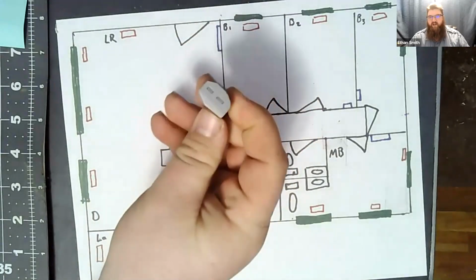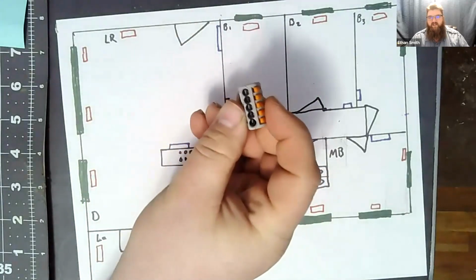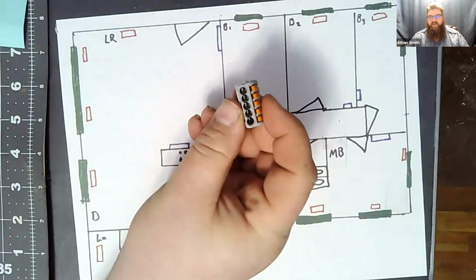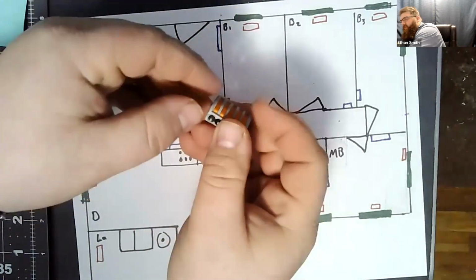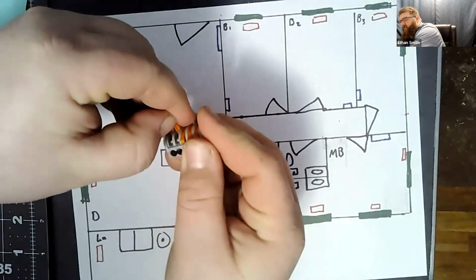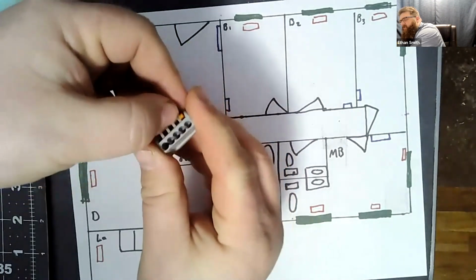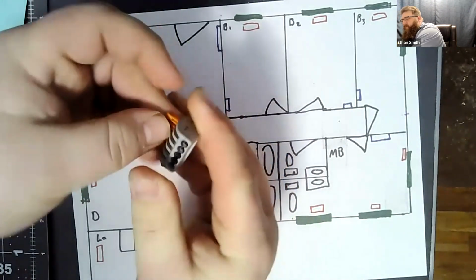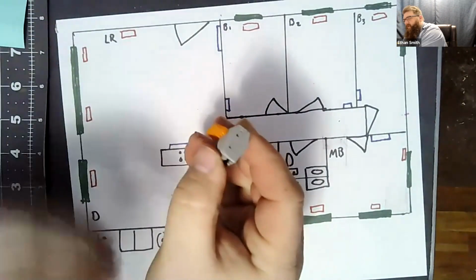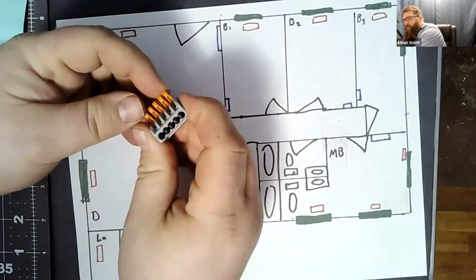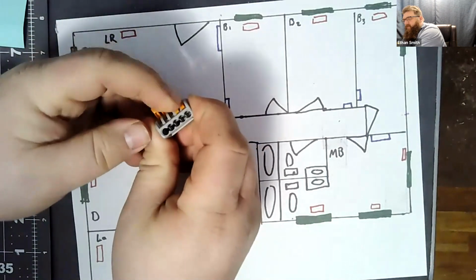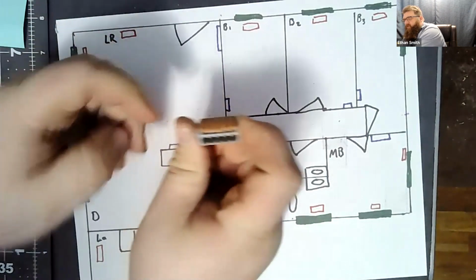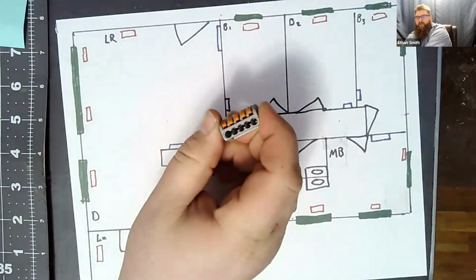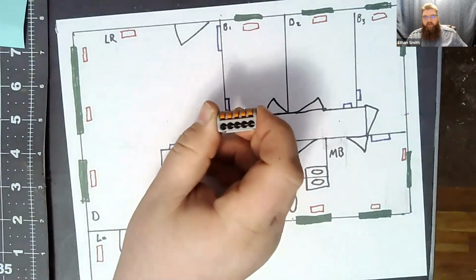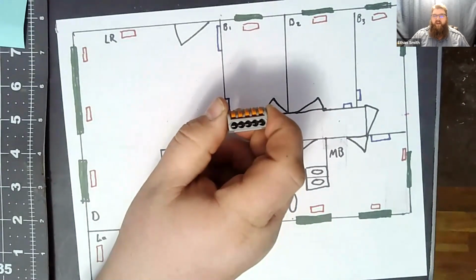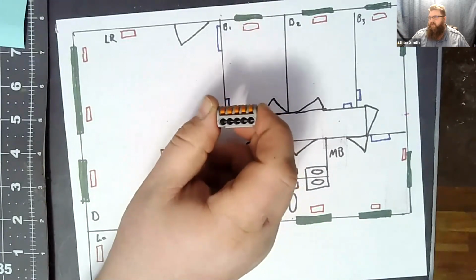So these are the clamp style connectors. You can see it's got positions for up to 5 wires in there. The way these work is you take all of those connections to the open position, which is at 90 degrees. You will insert your wire and then slap it down. Those will clamp all those wires together. That gives you a nice firm connection if you've got to do more than 2 wires in that wiring terminal.